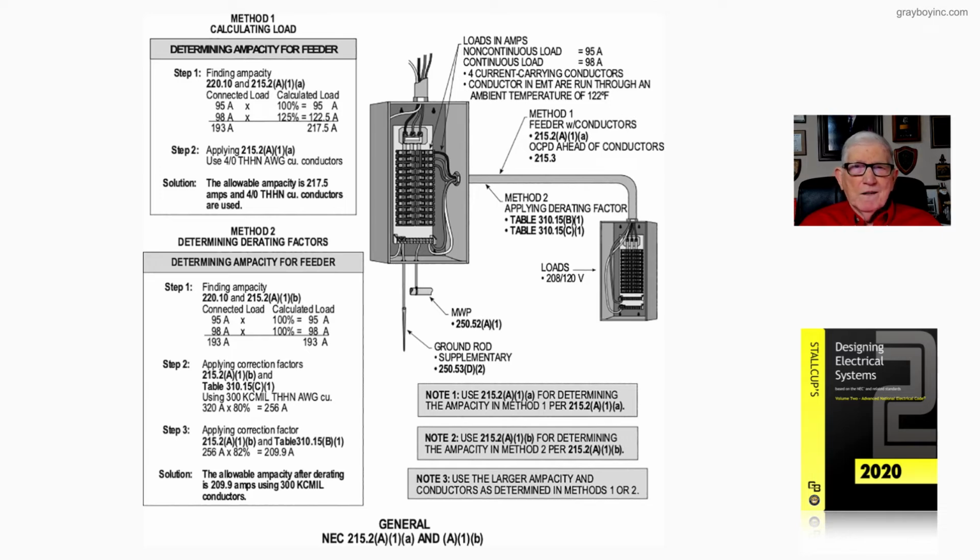You can't saw it out and give it a haircut, in other words. So you could buy a kit and stab larger lugs under these existing lugs to terminate it, or you'd have to route it a different direction in a different manner to get away from that 122 degrees Fahrenheit, so you wouldn't have to derate so much, or maybe not at all, see.